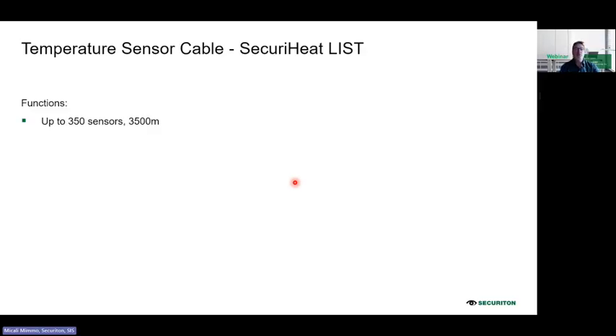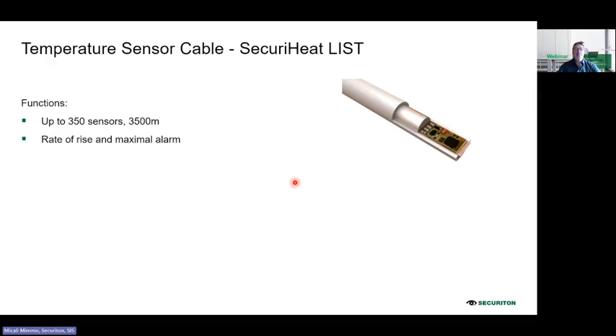Well, just a resume of this temperature sensor cable. We have up to 350 sensors, so we can reach up to 3,500 meters with one controller. The system is rate of rise and maximal alarm, so we have two conditions. The first condition determines how fast the system can react during an increase of temperature, but we can also set a maximum temperature, which can be between -40 up to 85 degrees. This is also important, that we have a setting of a maximal temperature. Then we have temperature values for each sensor available. So each sensor is reporting the real temperature to the operator. Then we have the possibility to have a redundant operation. I will show you later in the system design how we can do a redundant design.